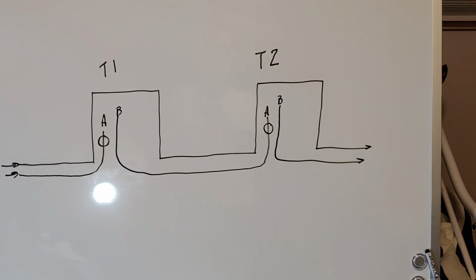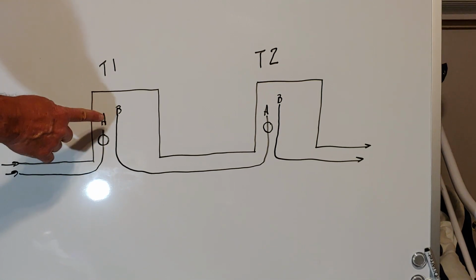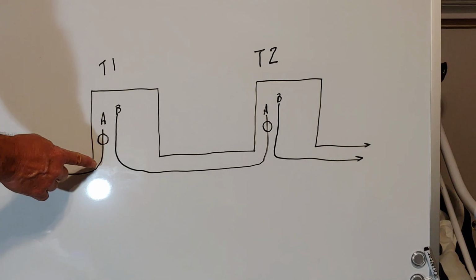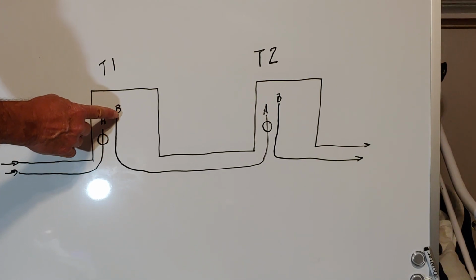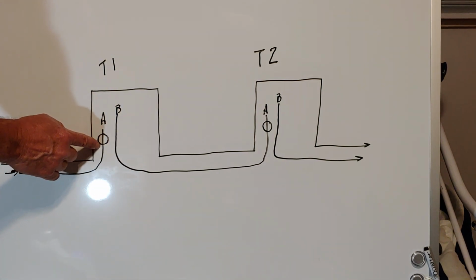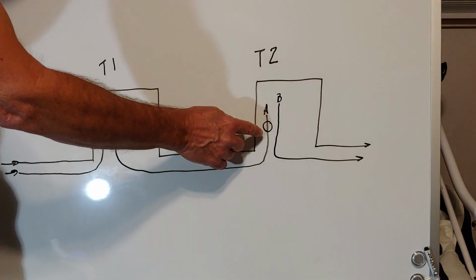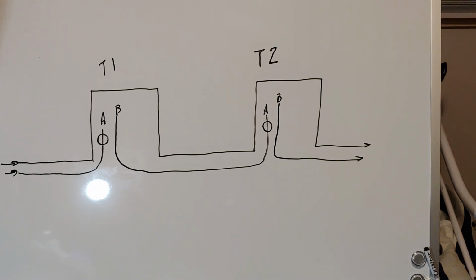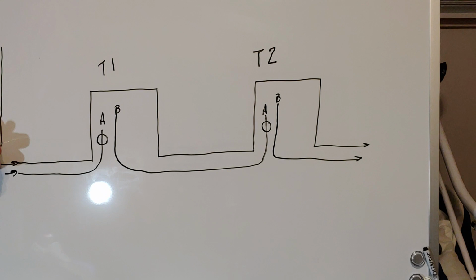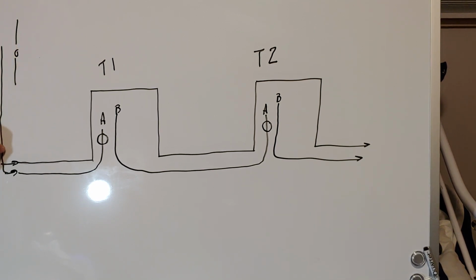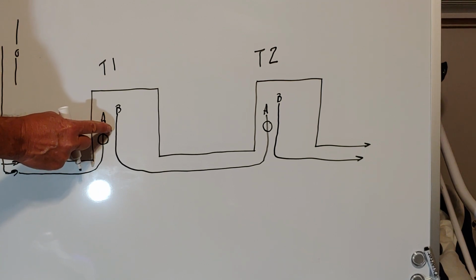And of course I can have transformers continue on as far as fault indicators and how many ever I need in the line. Okay, if you'll notice in the picture right here, the drawing that I have up, excuse me while I get over here, that the fault indicator really is sensing everything. So if I have inbound cable here and it goes into A, and remember it feeds through the transformer and goes out B, then the A indicator is also monitoring the transformer. Same with this one. So if I have a fuse blown here, draw this in. If I have a fuse blown, designates open, not only is the cable being monitored going into the transformer, but also the transformer itself.